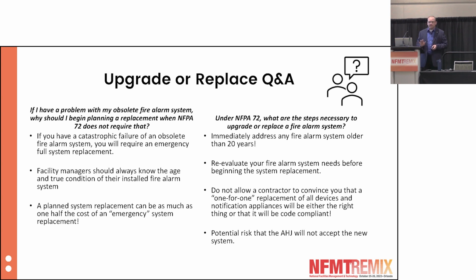I cannot underscore that enough, right? If anybody uses that term to you, "I'm just going to do a one-for-one replacement, we'll get it all up to date, you'll be fine," that is a lie. The codes have changed, the needs of our buildings have changed. We have to put some thought into this, because what you'll find is when you get to the end of that and the AHJ can't sign off on it or can't accept it, one of two things is going to happen. One, you're going to have a very costly upgrade and change order to fix that, or two, a very lengthy, painful process to get your system back into a certificate of occupancy.